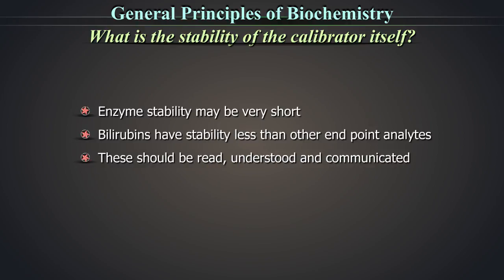Multi-calibrators contain several analytes. Different analytes in multi-calibrators will have different stabilities. For instance, the enzyme stability may be very short. Bilirubins may have stability less than other endpoint analytes. These should be read, understood and communicated.